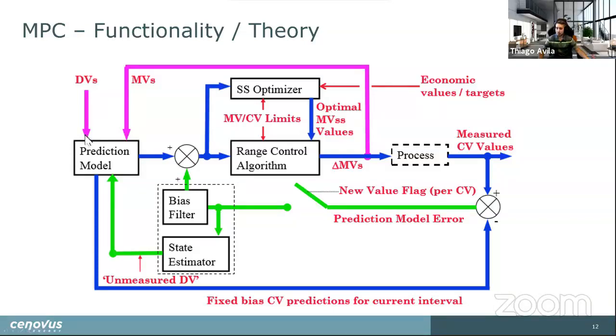With a traditional single input, single output controller, you've got a target that you've set and it comes in. Feedback from some part of your plant or process. The difference of these two terms is the error. And then your PID controller looks at the proportional integral and differential values that the engineers set up and then the controller determines an output. An APC controller is quite a bit more sophisticated and because it's looking at such a bigger picture, it is quite a bit more complicated. We'll break each one of these parts down in this presentation and talk about what they bring to the pie. But in general, you have a prediction model that takes all of your disturbances, all your manipulated values coming in, as well as your plant values for your controlled variables.